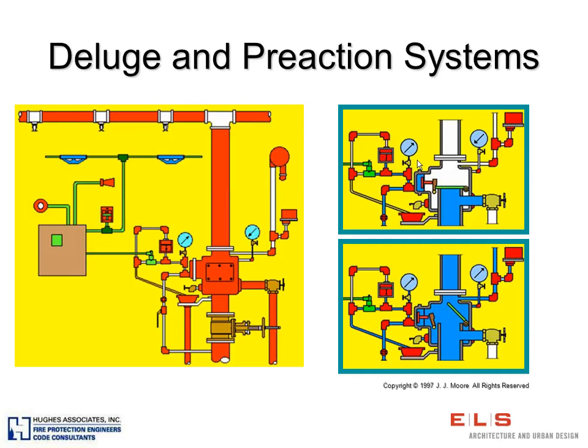So my photo here, this one on the top right, looks just like the dry pipe. It's wet under here, but it's dry above here. But instead of there being air in here, there is a tie-in to detectors. And those detectors send a signal to this panel. So, the smoke detector detects smoke, sends a signal to this panel, tells this valve to open, and you get water flow in your system.